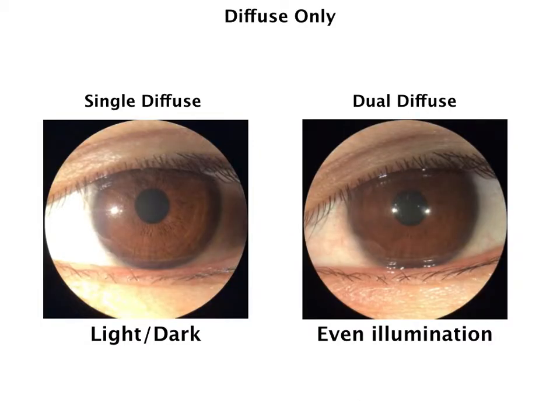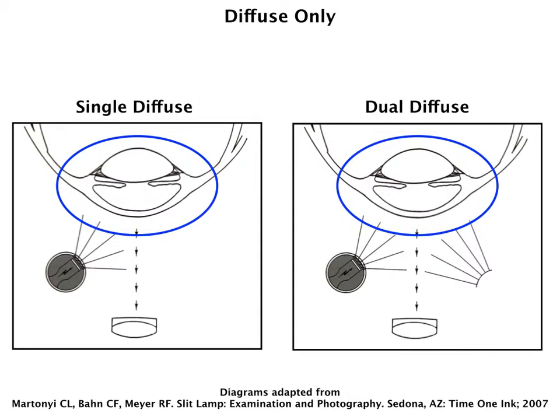For a lot of times when we're doing external photography, we just want a diffuse light with no slit beam on. There are two choices: a single diffuse light attached to the slit tower, or a dual diffuse light. One of the problems with a single diffuse light is that there's a very bright area and a very dark area of the photograph. Most of the time it's better to have even illumination to improve the overall quality of the photograph. Here's the diagram of the single diffuse and dual diffuse illumination.